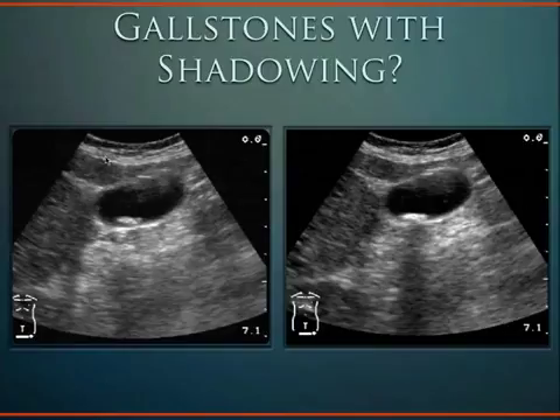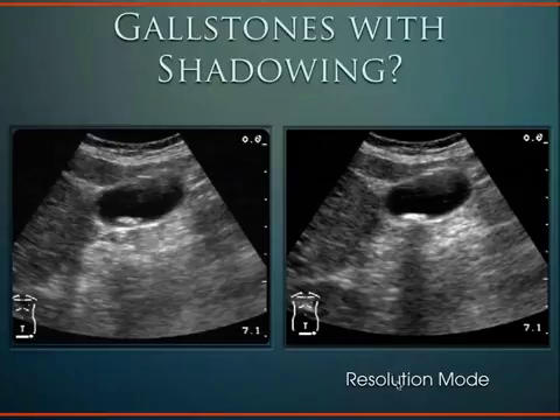So you see, when the sound is coming out here, it reaches this gallstone, but it's able to penetrate right past it. Yeah, that word penetration should clue you into the frequency adjustment. Because over here, the sound comes along, but it can't penetrate past this gallstone, and so there's a shadow that comes down. So what we did was we went to the resolution mode, or turned up the frequency. Down here we might be on the penetration mode, or lower frequency. To put this into numbers, this might be down around 1 megahertz, and this could be up around 5 megahertz. So see how frequency can cause more attenuation of the sound, thereby helping us confirm that yes, indeed, that is a gallstone because it shadows.